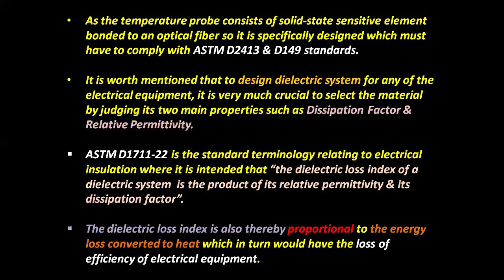As the temperature probe consists of a solid state sensitive element bonded to an optical fiber, it is specifically designed to comply with ASTM D2413 and D149 standards. It is worth mentioning that to design a dielectric system for any electrical equipment, it is very crucial to select the material by judging its two main properties, dissipation factor and relative permittivity.